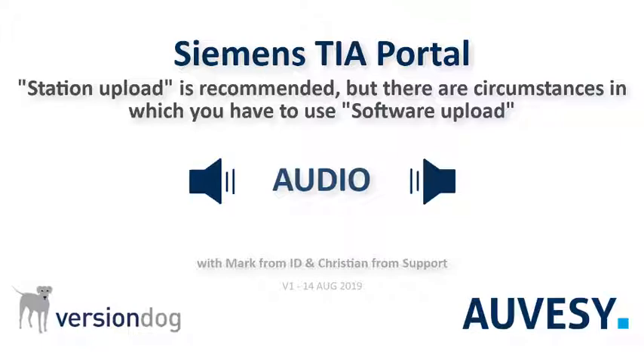So that leaves people who have 1200s but also 300s and 400s without the possibility to use Station Upload. Yes, and these are the people for whom Software Upload is still a good solution. The minimum TIA Portal software requirement is 13 SP1, isn't it? You're right — TIA Portal 13 SP1 up to the version before 15.1.